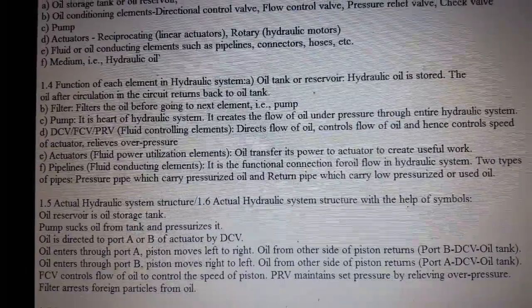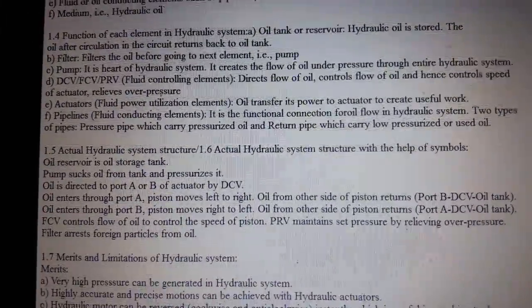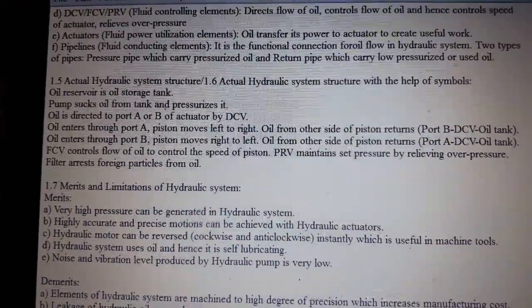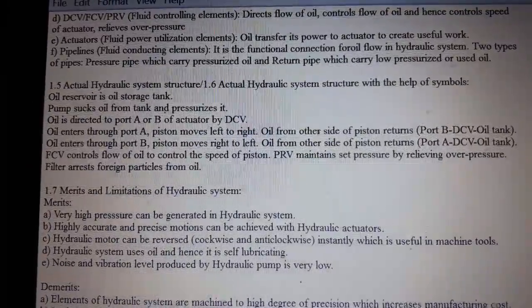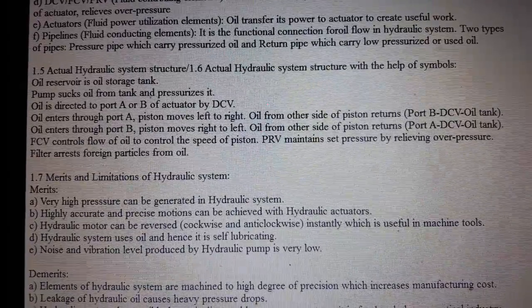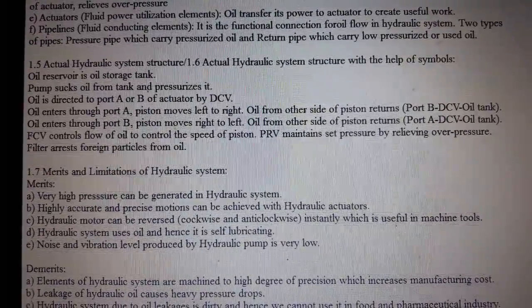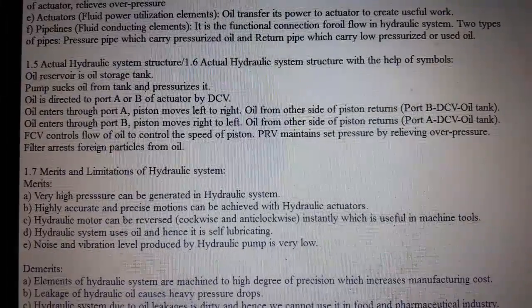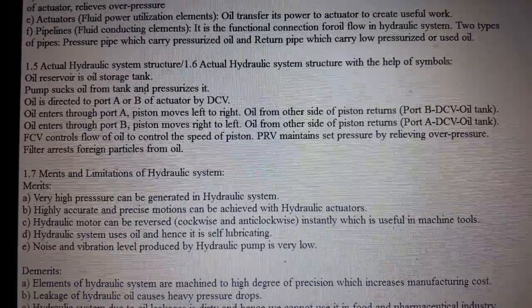Actual hydraulic system structure with help of symbols: the oil reservoir is the oil storage tank. The pump sucks oil from the tank and pressurizes it. Oil is directed to port A or port B of the actuator by the DCV. When oil enters through port A, the piston moves from left to right. Oil from the other side of the piston returns through port B, then through the DCV, then to the oil tank.